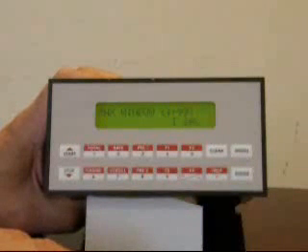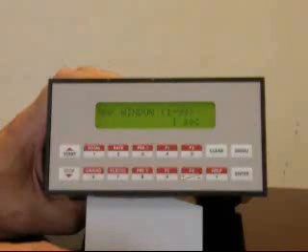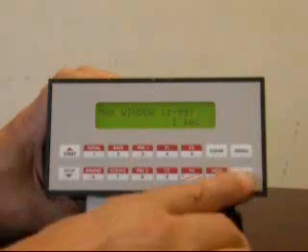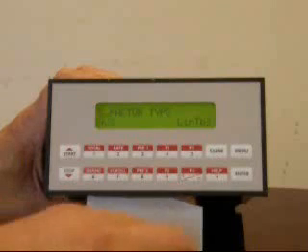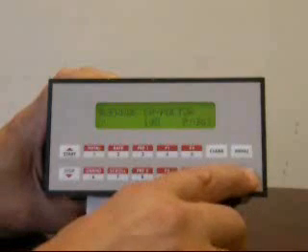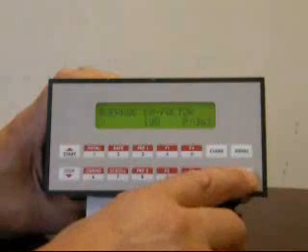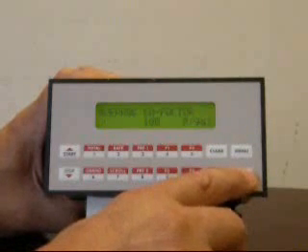Next, there's a menu offered for window settings. This is the maximum period of time that the indicator will wait for a pulse to come in before assuming that the flow rate is zero. We're going to use the one second selection since the frequencies from flow meters of the turbine type are normally between 10 hertz and 1000 hertz. Waiting one second is adequate to determine there is no flow. You may remember the selection of k-factor type from the easy setup and we're going to leave those selections where they were. Similarly, the k-factor selection is the number we entered previously.